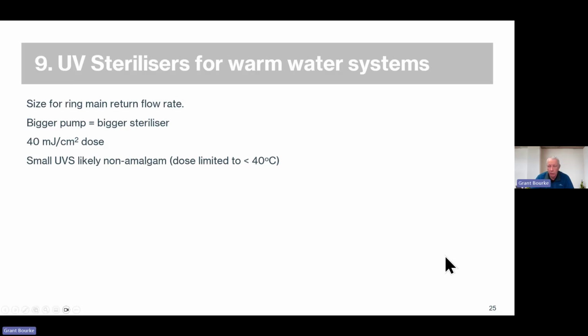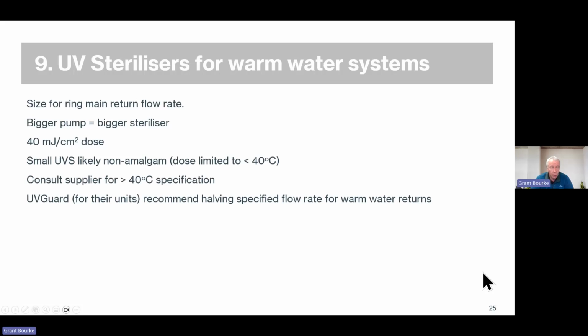So what you need to do is, if you want to use a smaller system, which most of us do, you need to get off to your supplier and ask them, what's going to happen if I put 50-degree return water through your system? And hopefully they can tell you, as UV Guard told me for their units, take our specified flow rate and halve it. Now that's for the UV Guard units. If you're using a different unit, you need to talk to your supplier and see what they say. They may say you can't use it at all, or they may give you some other rule of thumb to work with, as UV Guard gave me.